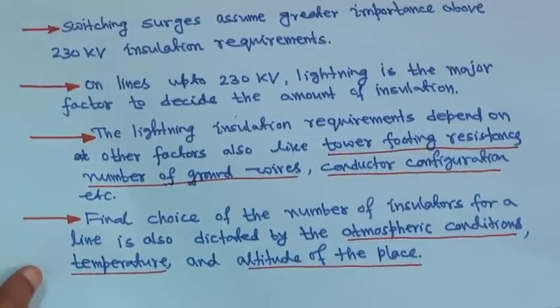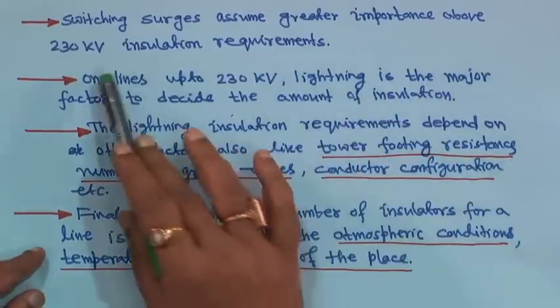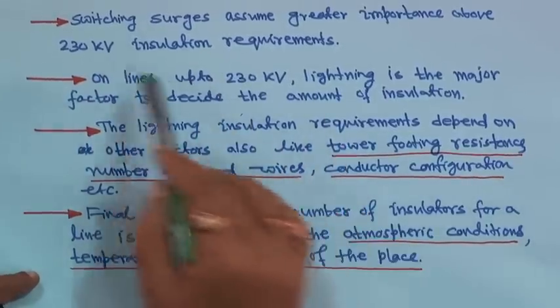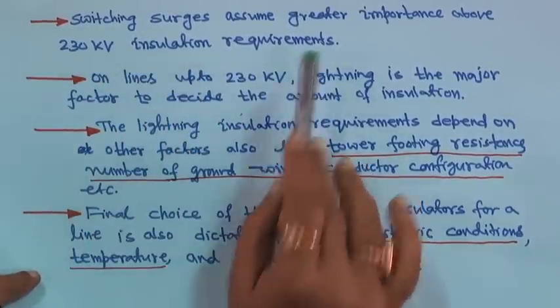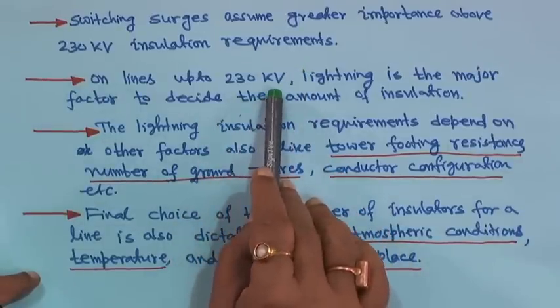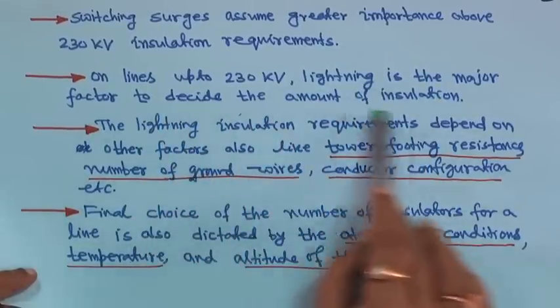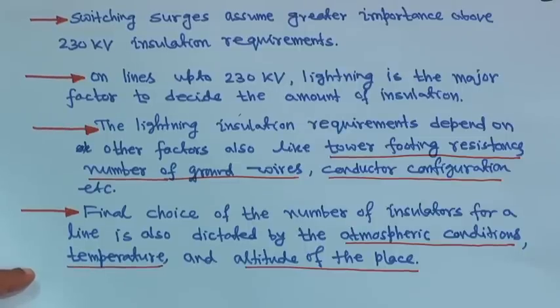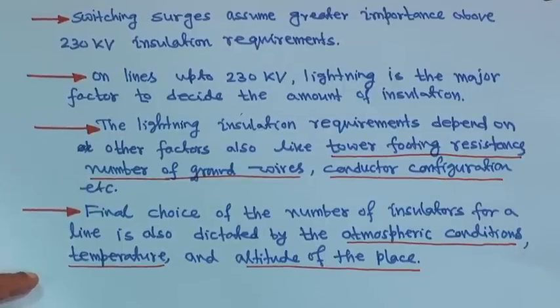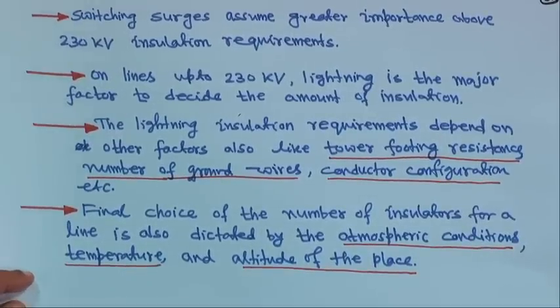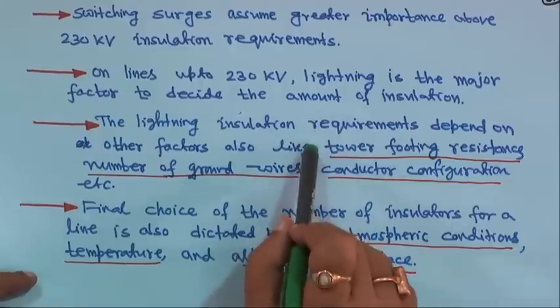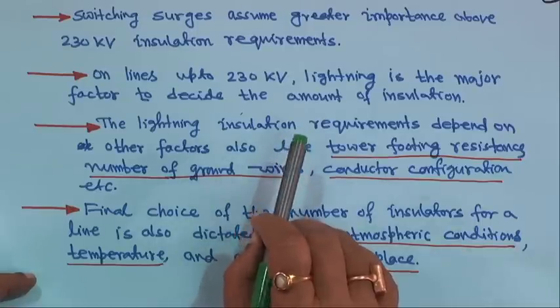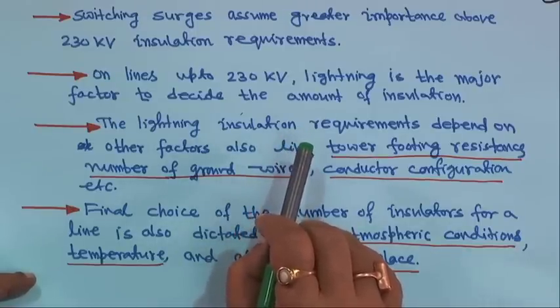Switching surges assume greater importance above 230 kV insulation requirements — in our country 220 kV or above, then 400 kV lines. On lines up to 230 kV, lightning is the major factor to decide the amount of insulation, because lightning strokes are very common phenomena everywhere. If a lightning stroke hits the top of a tower, you do not know how much it can affect your equipment or apparatus at the substations.